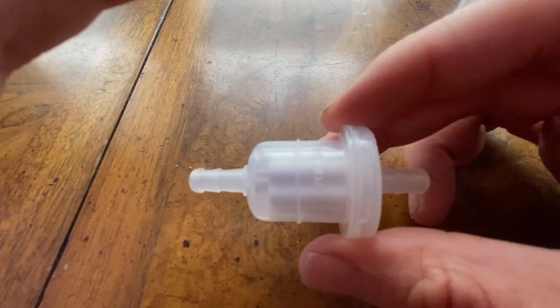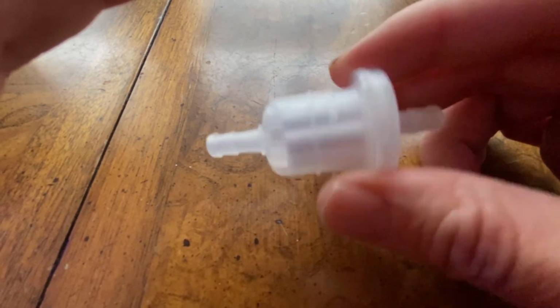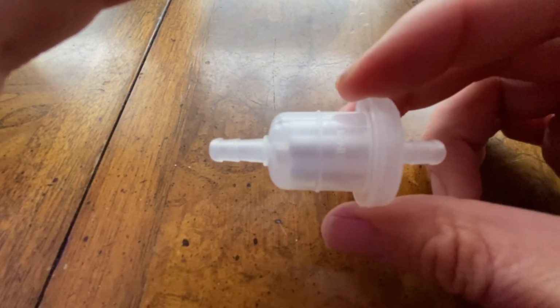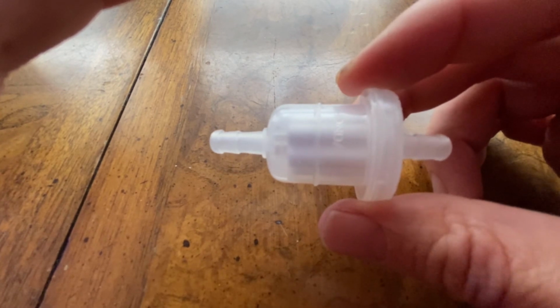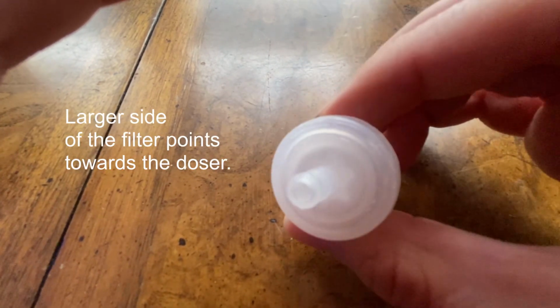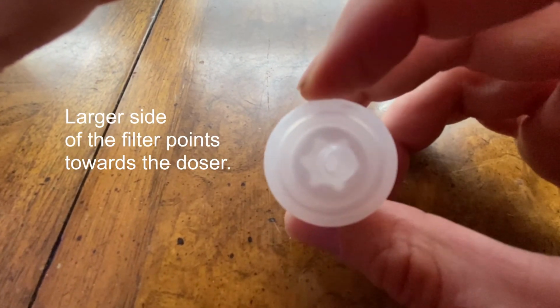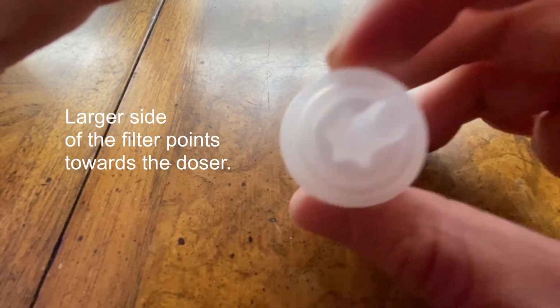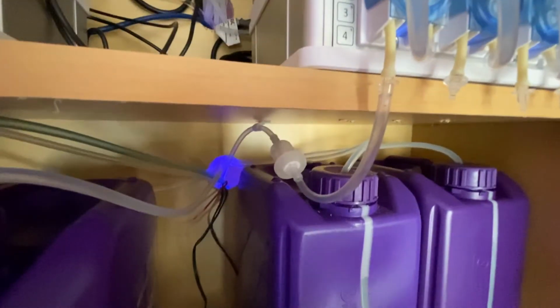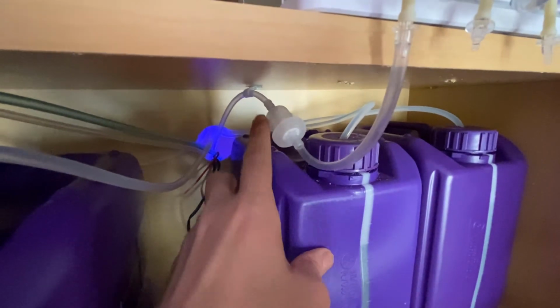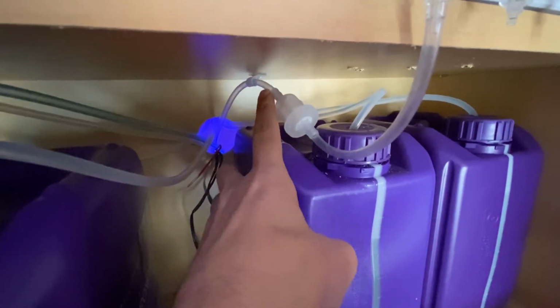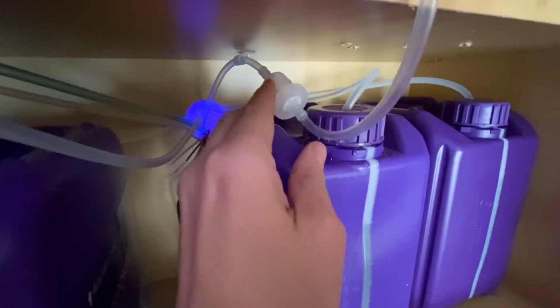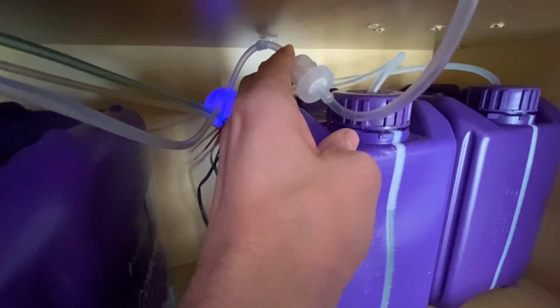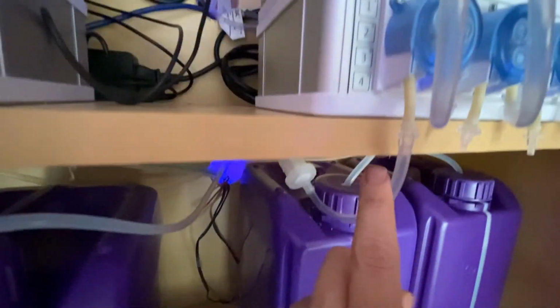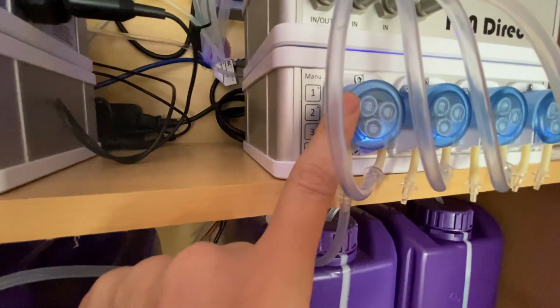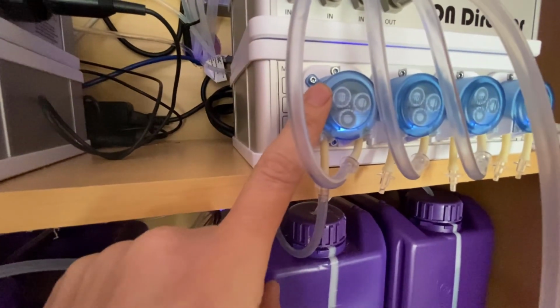Now, how do you install it? It's pretty simple. You could try to read the arrows that are on it. There's a nice arrow that says a specific direction, but really all you need to do is make sure that this side, the larger side, is pointing towards the doser. So now I've connected the supply side. This is going down to my sump, right where my return pump is. There's my filter. Easily I can remove it. And then it comes up into the supply side of my water sample dosing pump.